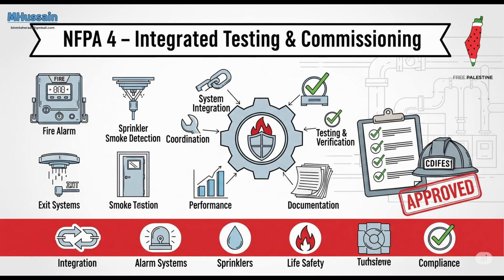And the standard insists on testing the whole chain. Very clearly, it states, end-to-end testing shall be required. That means testing the full sequence, from the initial input, that smoke detector going off, all the way through every intermediate step to the final intended output, elevators recalling, doors releasing, smoke control starting up, maybe a suppression system discharging. So verifying the entire pathway, not just bits and pieces. The whole critical pathway. No skipping steps, no assuming connections work. You test it all. Okay, so this really robust test plan is mandatory for new systems.